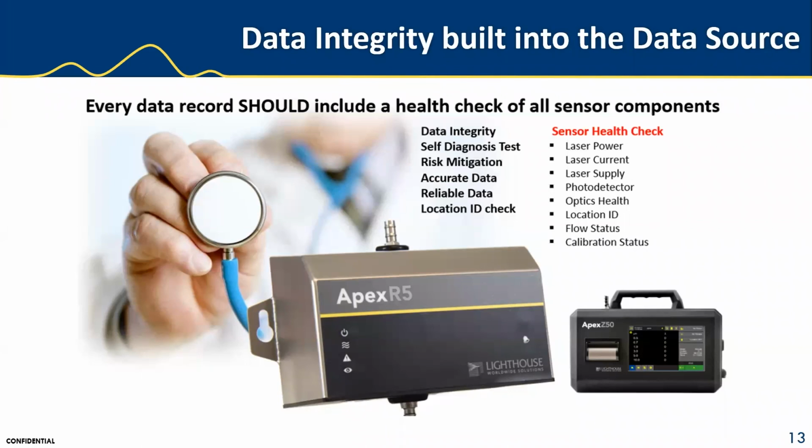So, as we have seen, this is one example of ensuring the integrity of the source data. All bad data will be marked as such and discarded from the batch report. The particle counter will signal if the contamination is severe enough to warrant a service.